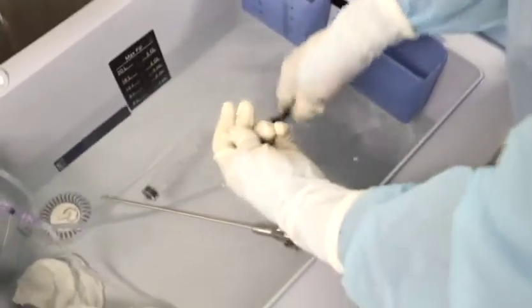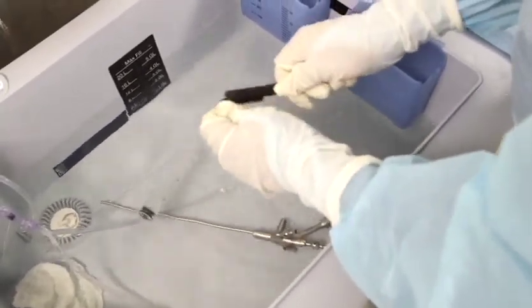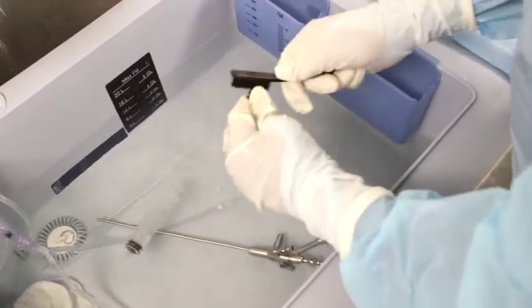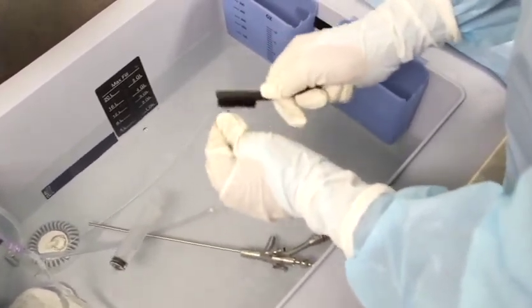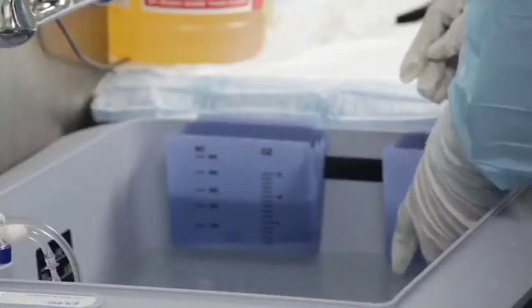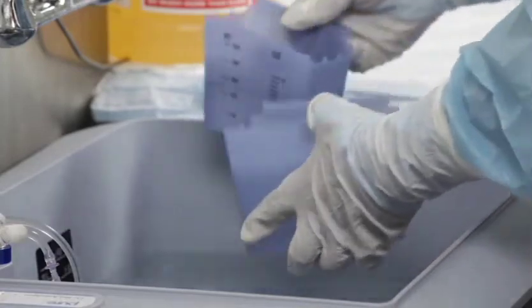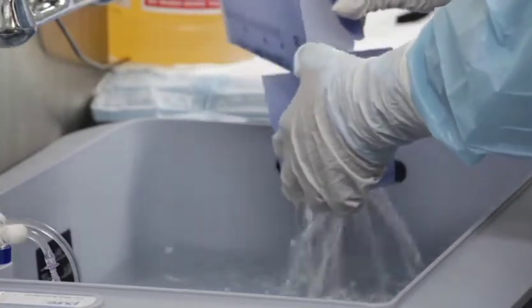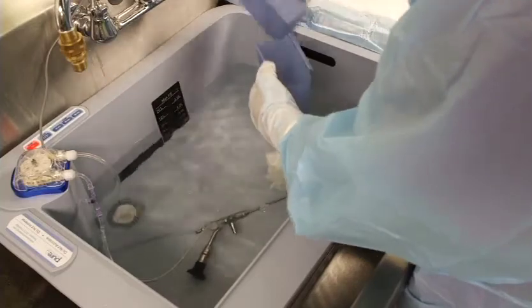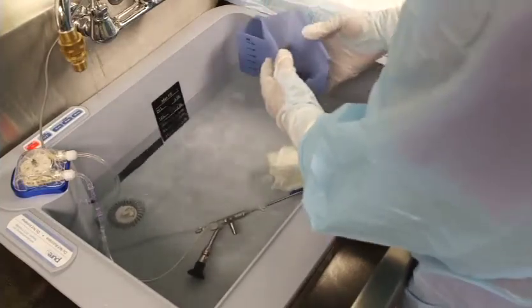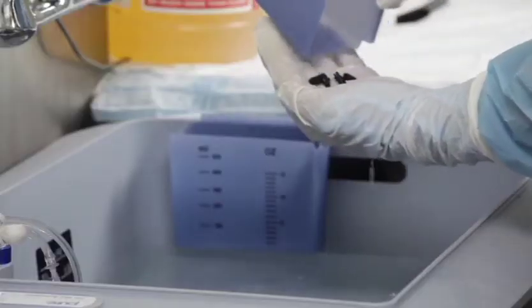While the endoscope is soaking, thoroughly brush the attachments with the brush size that corresponds to the channel size of the endoscope's attachment. Rinse attachments with processed water and keep them in one place to ensure they are with the endoscope for final assembly. The endoscope cannot be used for a surgical procedure if the parts are not with the scope. The rigid endoscope is now ready to be cleaned.